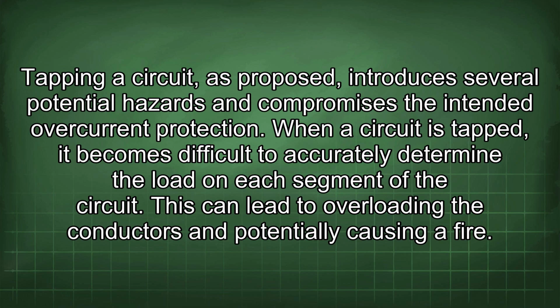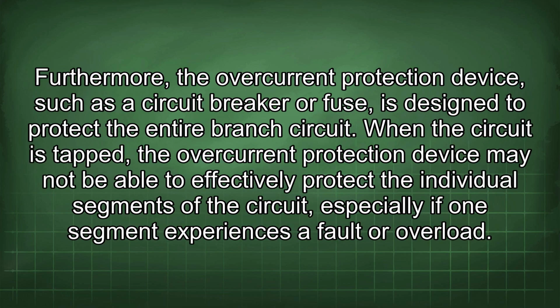When a circuit is tapped, it becomes difficult to accurately determine the load on each segment of the circuit. This can lead to overloading the conductors and potentially causing a fire. Furthermore, the overcurrent protection device, such as a circuit breaker or fuse, is designed to protect the entire branch circuit. When the circuit is tapped, the overcurrent protection device may not be able to effectively protect the individual segments of the circuit, especially if one segment experiences a fault or overload.